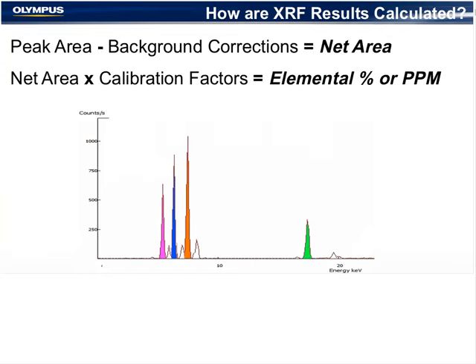The detector captures the spectrum of energy as displayed here, and beyond calculating the chemistry from the spectrum, the elemental values can be used to determine the grade match. What's happening in the algorithm basically is we're correcting for background and interferences from other elements. Once we get a net signal for each element, we're able to apply our calibration algorithm and determine the percent concentration. This process, as far as the user is concerned, is really real time. The test starts and the answer is directly displayed.